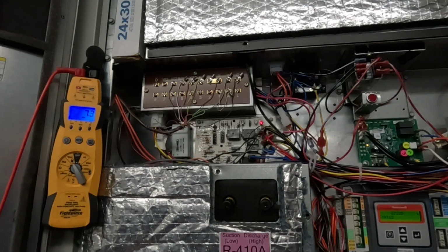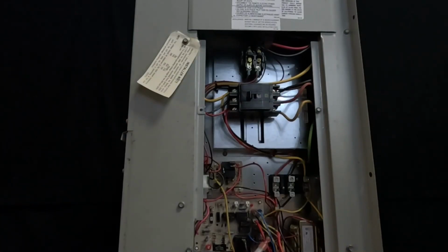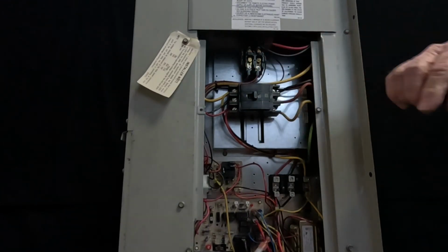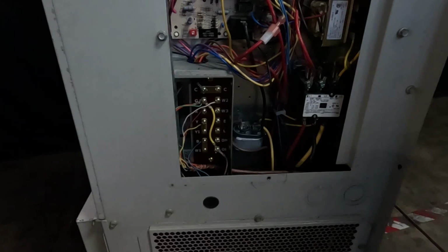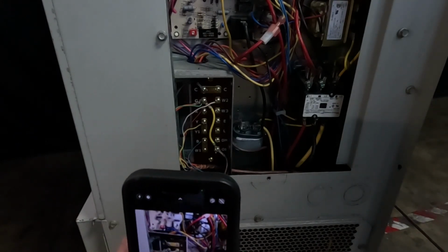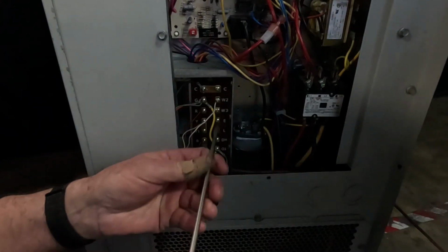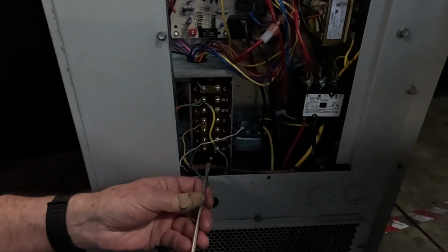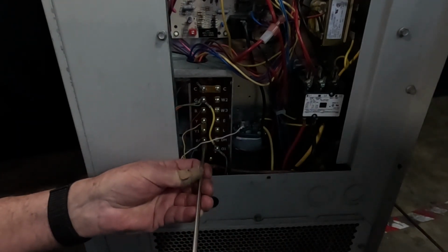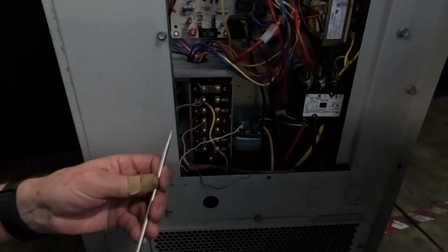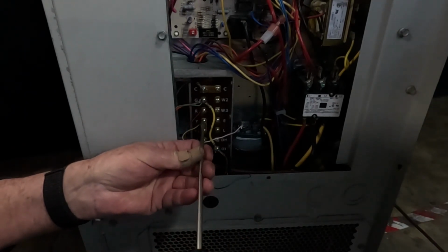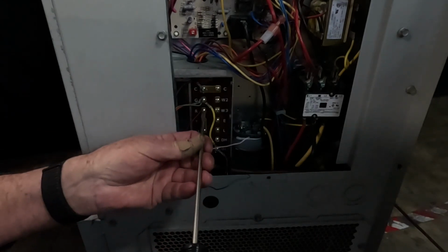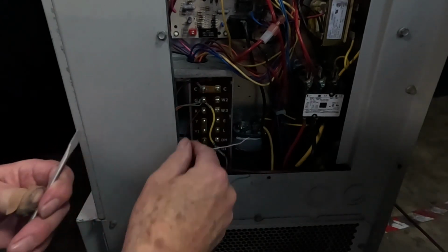Let's go further. To determine if the problem is the unit or other, turn off the breaker. Take a photo of the low voltage terminal block and disconnect all, not just some, all connected stat wires on the low voltage terminal block. Do not remove or disconnect any Bard wires landed on the low voltage terminal block. That may be a different step depending on what we find.